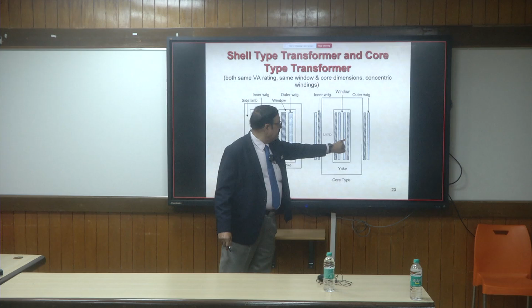Look at the core type transformers. The core type construction transformer or choke has the yoke going round and round throughout, and the coil is split on two sides. Now for the same design of voltage or current, the window area is going to be the same in both, because this has one inner winding and one outer winding, and this has 50% plus 50%, 100% of outer, and 50 and 50, 100% of inner. So the window area is the same.